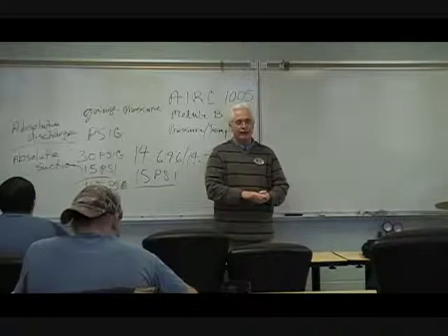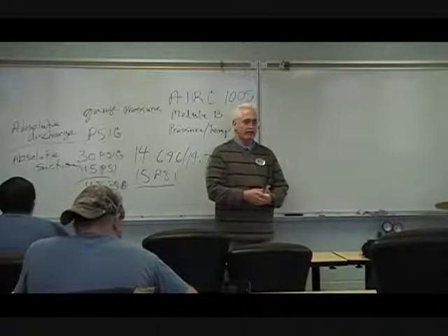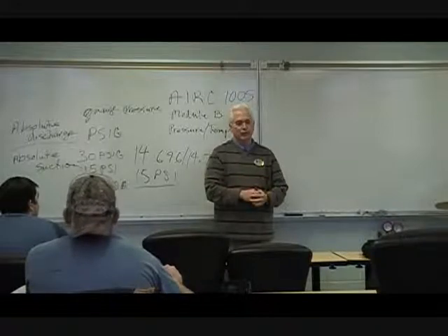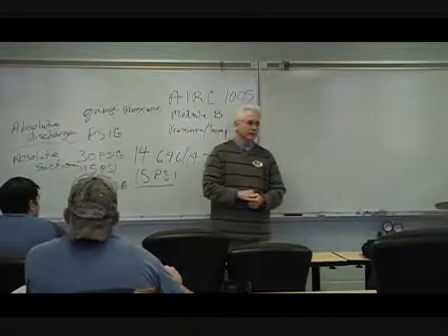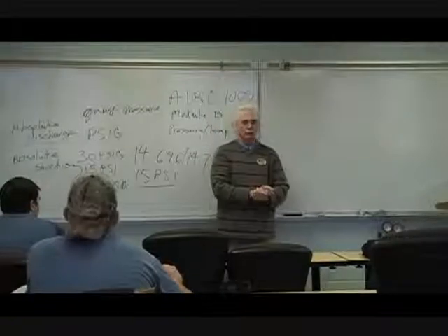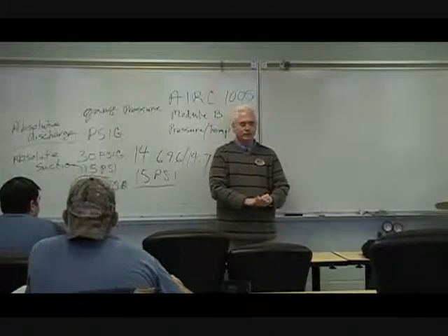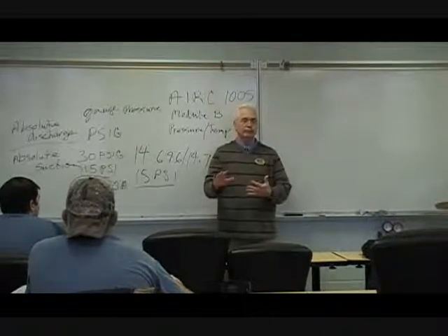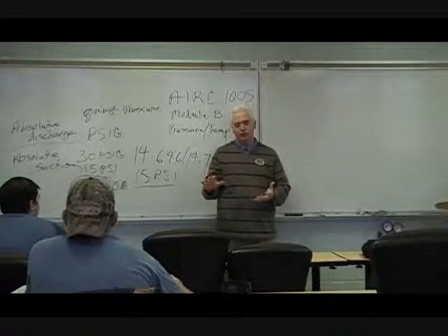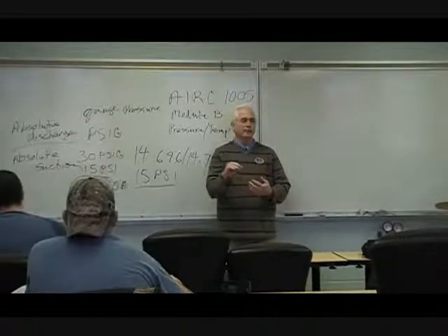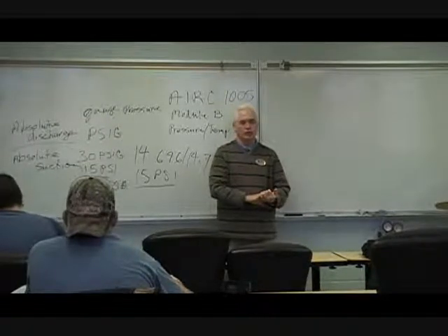But just keep in mind that when you're dealing with a refrigeration or air conditioning system, measuring pressures is paramount. We gave each one of you a pressure temperature chart. There's one thing I want you to remember about pressure. When it comes to refrigerants and refrigeration and air conditioning systems, at any given pressure, for any given refrigerant, you're going to have a corresponding temperature. That's one of the laws of physics, one of the gas laws. There's always a specific fixed pressure-temperature correlation.